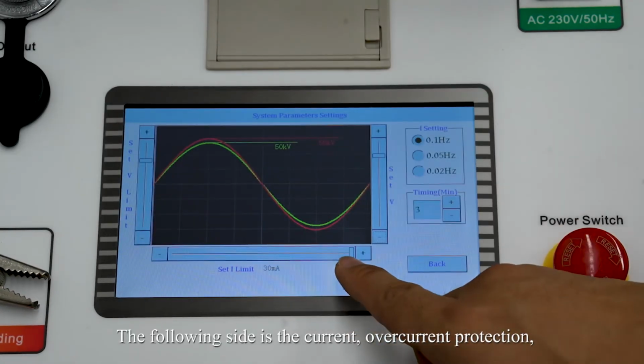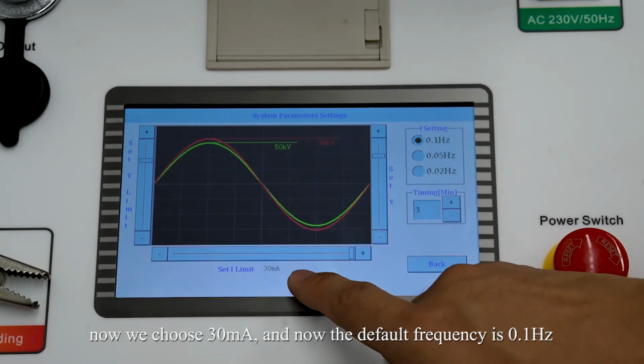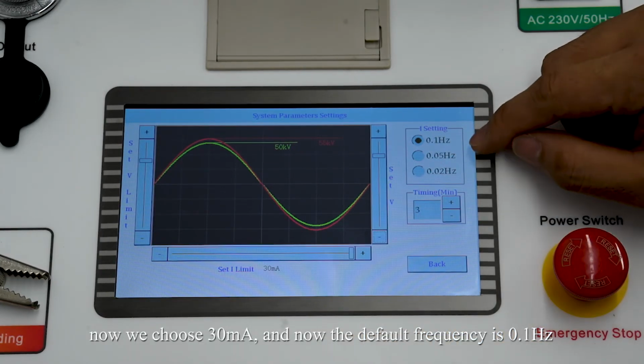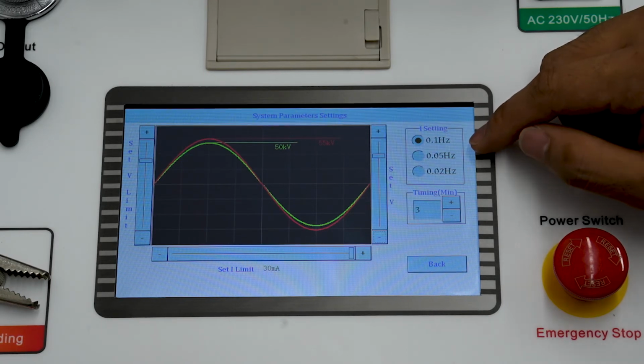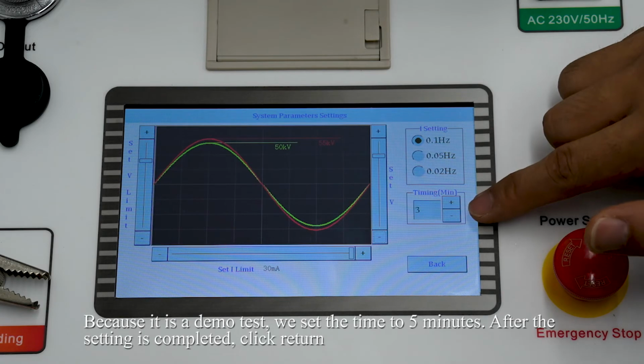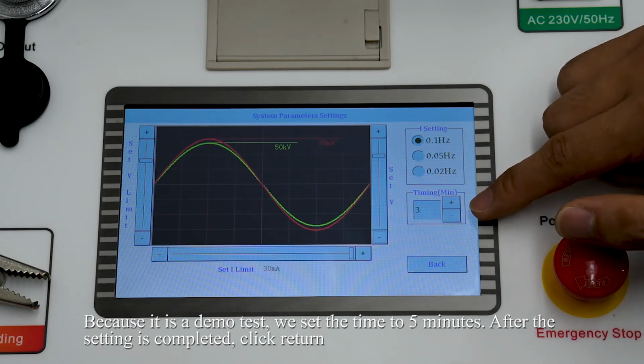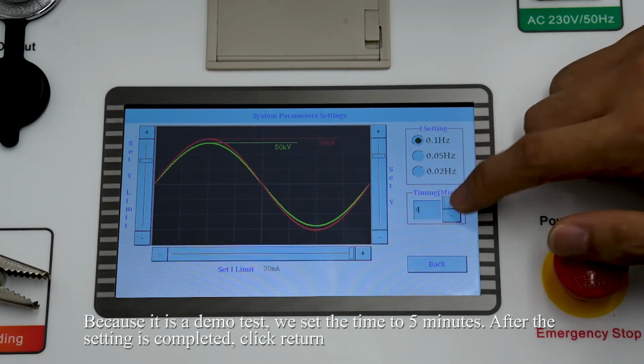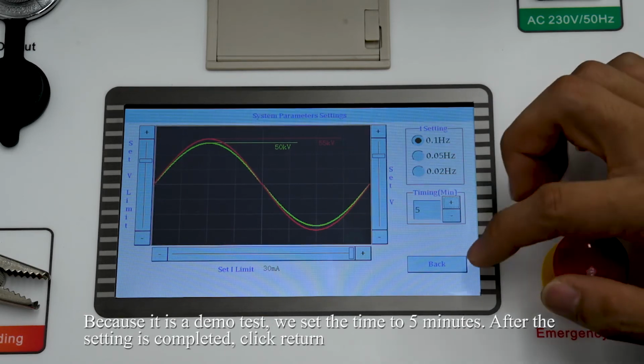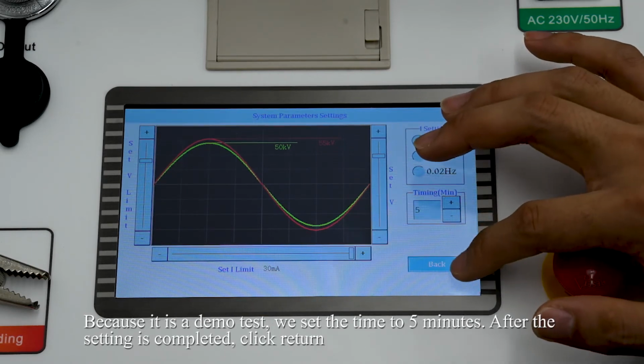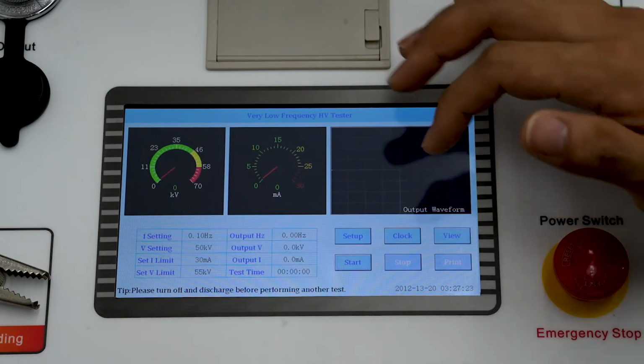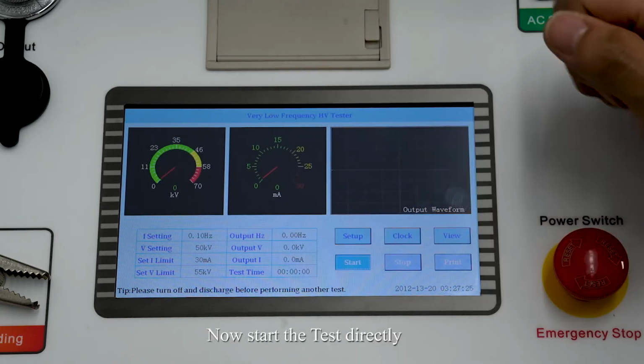The following side is the overcurrent protection. Now we choose 30 mA, and the default frequency is 0.1 Hz. Because it is a demo test, we set the time to 5 minutes. After the setting is completed, click Return. Now start the test directly.